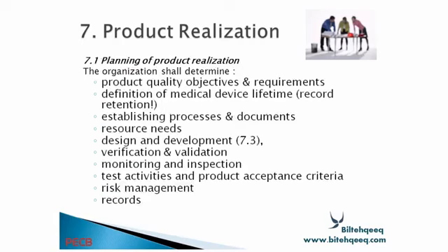Planning of the product realization. The organization shall determine product quality objectives and requirements, definition of medical device lifetime, record retention, establishing process and document resources needed, design and development, verification and validation, monitoring and inspection, test activity and product acceptance criteria, risk management records.